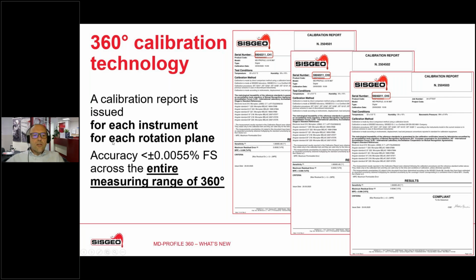Which accuracy are we able to reach with this MD Profile, with this calibration technology? We arrive at an accuracy better than plus or minus 0.0055% of full scale across the entire measuring range of 360 degrees. So you can rotate the MD Profile in space to any position, and you will have the same accuracy in any position. This is a great goal that we reached.